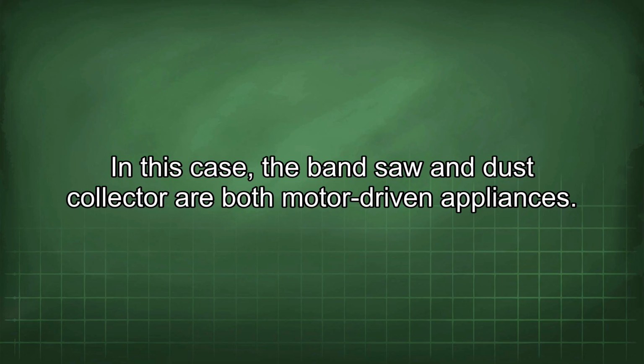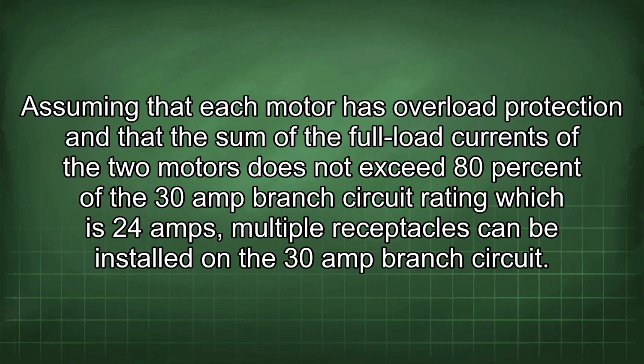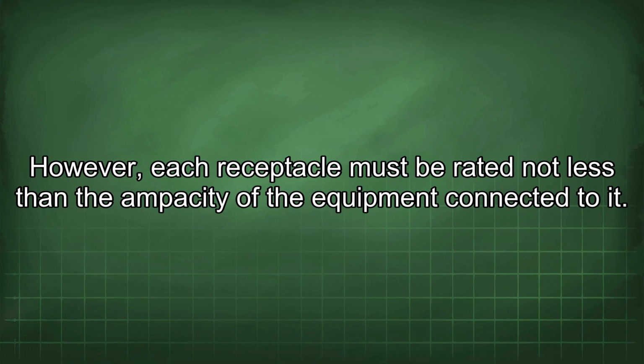In this case, the bandsaw and dust collector are both motor-driven appliances. Assuming that each motor has overload protection and that the sum of the full load currents of the two motors does not exceed 80% of the 30 amp branch circuit rating, which is 24 amps, multiple receptacles can be installed on the 30 amp branch circuit. However, each receptacle must be rated not less than the ampacity of the equipment connected to it.